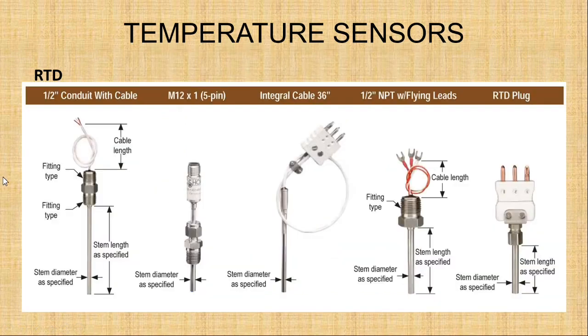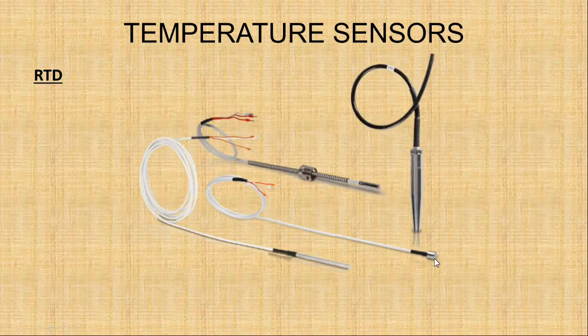Here are pictures of some that are out on the market. Looks like these are for sensing liquid or liquid medium of some types. It's got a pipe fitting. Here's the 3 wire. Looks like all these are 3 wire, and the various types of connections that they can use. These are sometimes referred to as banana plugs. Those are very typical, and you can't plug other types of sensors in those type of plugs, so it kind of meets a standard there. You can't mistakenly plug in the wrong type of probe. Kind of a bead probe there, in a way, with a small sensing tip. A lot of these probes will look very much alike. The thermocouples we looked at earlier and these, sometimes when you look at them, they look identical.